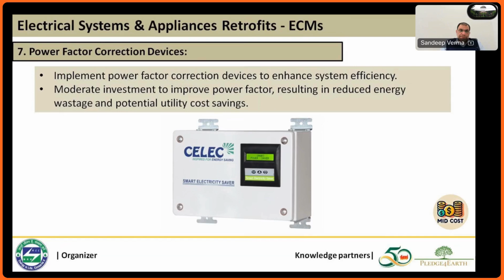You normally either draw reactive power from the grid, or alternatively generate it at site without much investment with the help of a capacitor bank and proper controls. Whenever you require reactive power, it can be catered locally. This helps in reducing the power drawn from the grid, and if we go into depth, it also helps reduce resistance losses or power losses that take place in the distribution system.